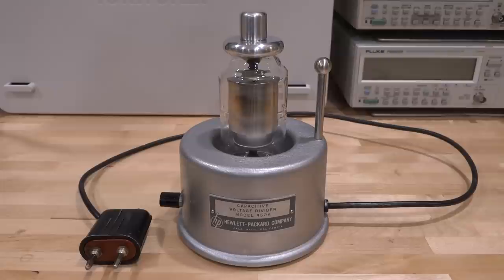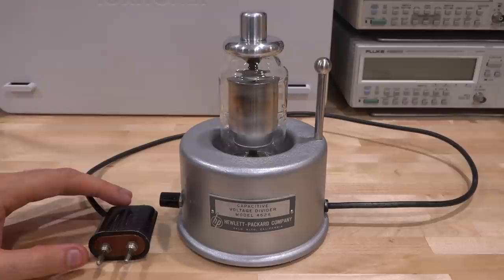If you guessed a capacitive voltage divider, you would be correct. This is an HP model 452a, and its job is really simple: divide an incoming AC signal by a predictable ratio using capacitive division. I'll talk about the theory in just a second. The idea is that you have a very high voltage AC signal coming in and you want to divide it down so you can connect it to something that can measure regular low AC signals at much lower value.